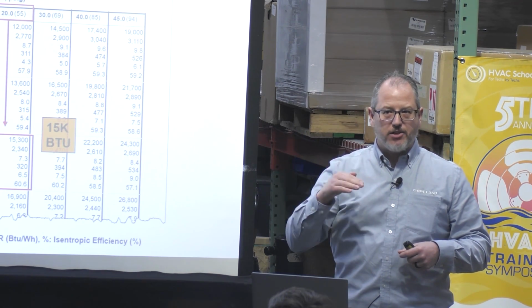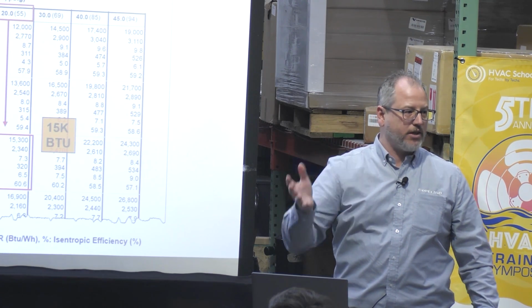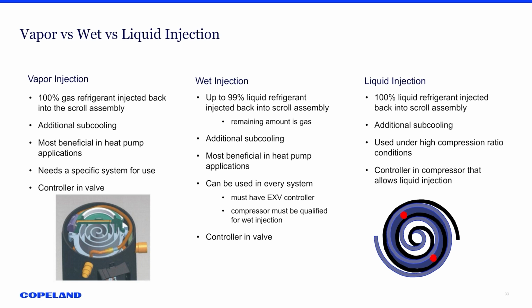You can put your information in, and it'll show you at those conditions, this is what your amp draw should be. For low temperature applications, we need to, because remember, when we're dealing with lower suction pressure, our discharge temperature, everything is running hotter. Our mass flow is lower, so we're not bringing as much refrigerant through the system. So we had to do something, and we came up with injection. So in the refrigeration world, we've used liquid injection for years. Okay? So we inject refrigerant into that scroll set in the mid-range of that scroll set, and it instantly cools down that compressor. And I'll show you a little diagram with a pressure enthalpy diagram, kind of how that works.